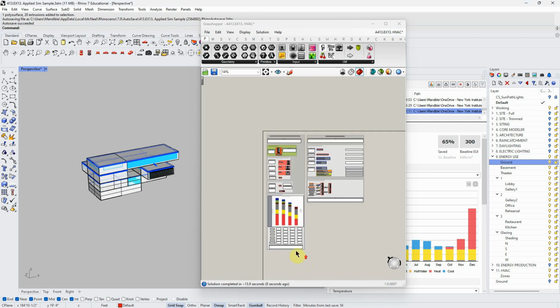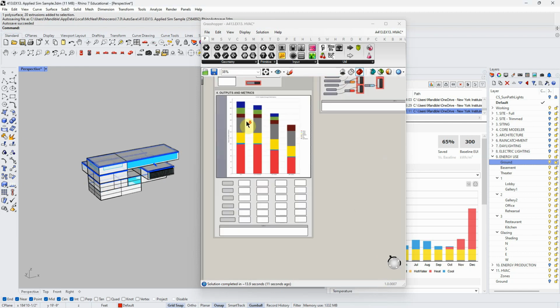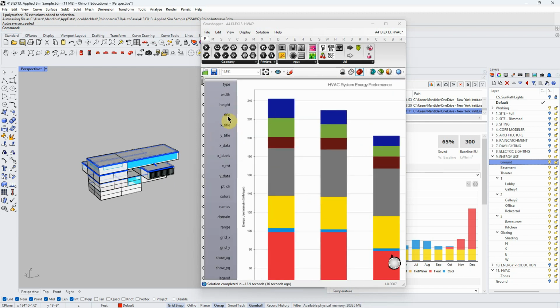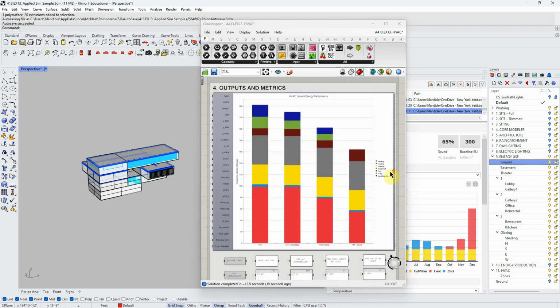And okay, so here are our outputs. This is a chart comparing, where we have the typical breakdown. This is our energy usage, so it's our site EUI, and we have it broken down into lighting and heating and equipment, etc. Then here, this is really the more interesting chart. We have each system type here, and then we're comparing the EUI. So our VRF, variable refrigerant flow heat pump with a dedicated outdoor air system, has the lowest energy usage and therefore the lowest carbon of any of them by quite a bit in this case.